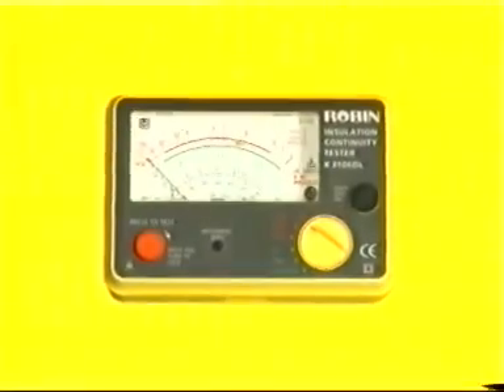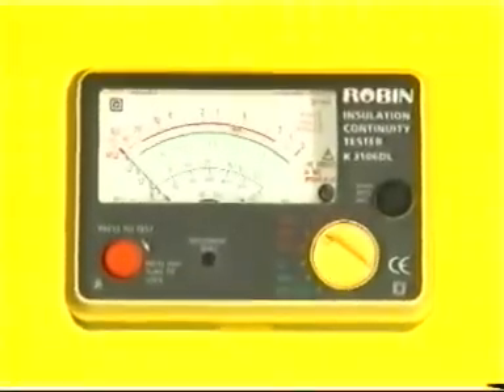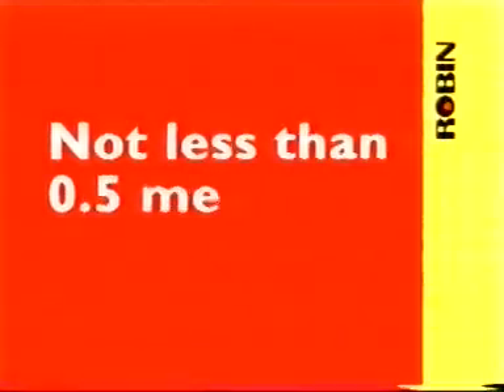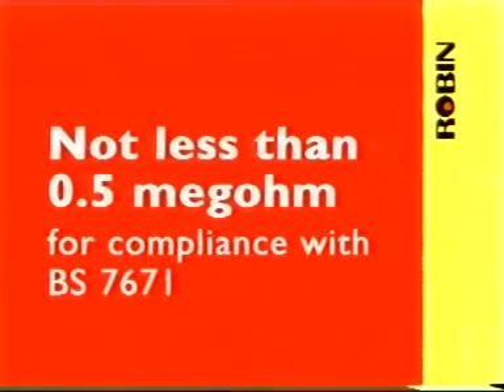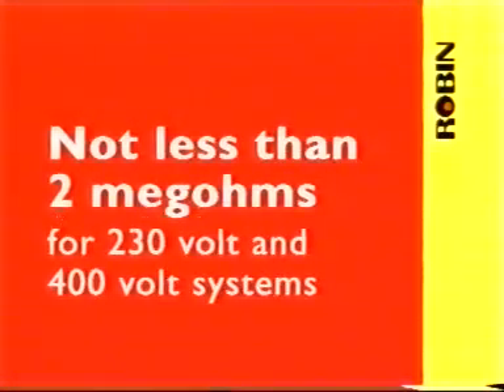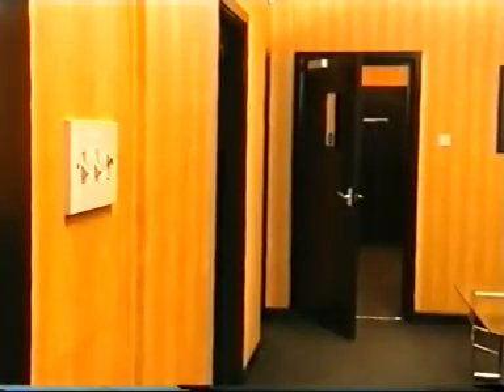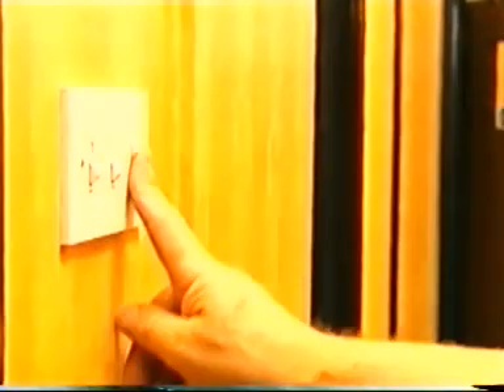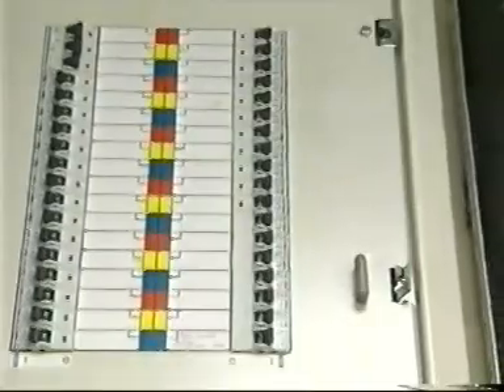The resistance between live conductors and between live conductors and earth must not be less than half of 1 megohm for compliance with BS7671. For compliance with IEE Guidance Note 3, not less than 2 megohms for 230 volt and 400 volt systems. Two-way switches must be operated in both positions to include all switch wires. 2 tests are therefore needed. Large or complex installations involving multiple circuits can be subdivided and tested in groups of lesser numbers of outlets.